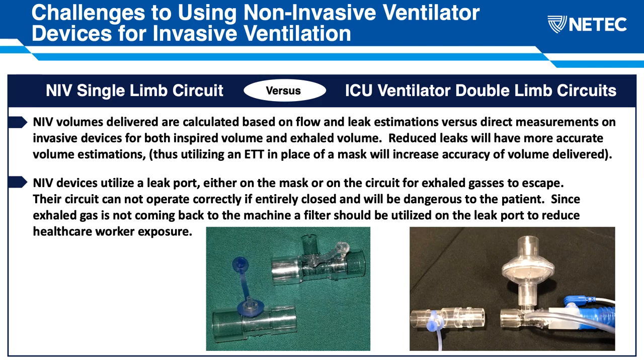Some of the manufacturers do make a leak port that can be changed out for one, as in the photograph here, that you can place a filter on. And that would probably be your best option. As Vikram had mentioned, these devices with that leak could be spreading the virus through the room. So this would limit the amount of virus and allow you to still utilize it invasively, but limit the leak that you have in there.